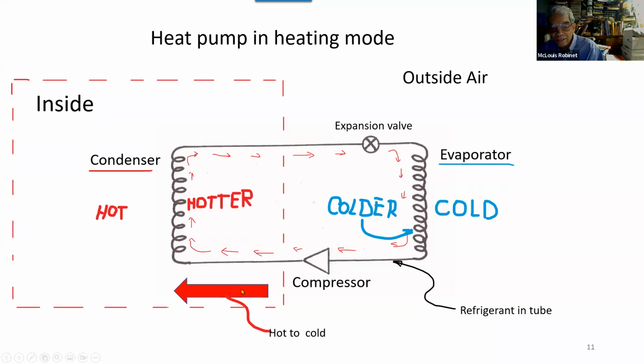So let's actually look at a heat pump in heating mode. Again, we have to follow the basic principle that heat travels only from hot to cold. If our purpose is to extract heat from the outside air, we live in a sea of thermal energy, and we can extract that energy provided that we create the conditions to do that. If we want to extract heat from the outside, regardless of what the temperature is, and dump it to the inside, we have to make this evaporator coil colder than the outside. You pick a temperature, regardless of what it is, and we'll extract heat if we make this colder.